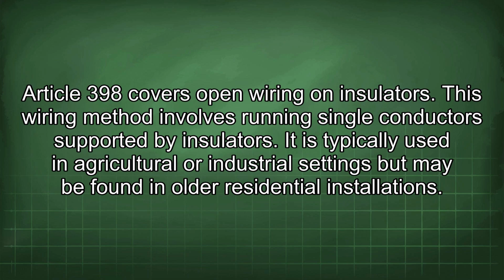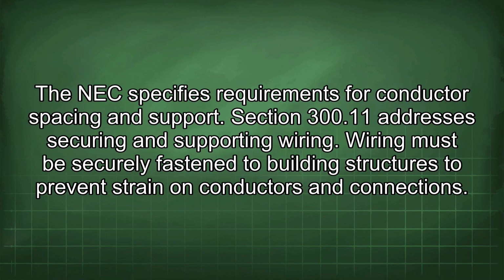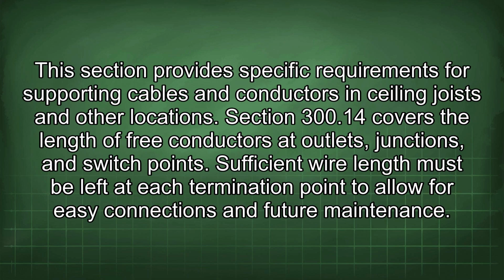Article 398 covers open wiring on insulators. This wiring method involves running single conductors supported by insulators. It is typically used in agricultural or industrial settings but may be found in older residential installations. The NEC specifies requirements for conductor spacing and support. Section 300.11 addresses securing and supporting wiring. Wiring must be securely fastened to building structures to prevent strain on conductors and connections. This section provides specific requirements for supporting cables and conductors in ceiling joists and other locations.